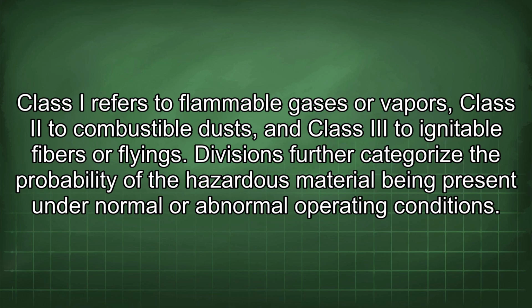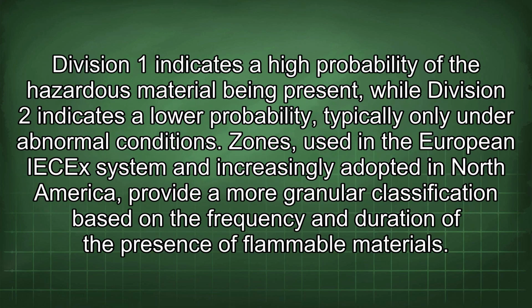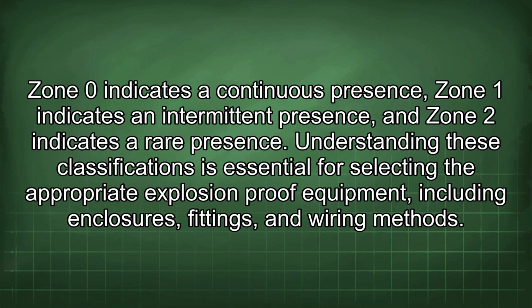Divisions further categorize the probability of the hazardous material being present under normal or abnormal operating conditions. Division 1 indicates a high probability of the hazardous material being present, while Division 2 indicates a lower probability, typically only under abnormal conditions. Zones, used in the European IEC system and increasingly adopted in North America, provide a more granular classification based on the frequency and duration of the presence of flammable materials. Zone 0 indicates a continuous presence, Zone 1 indicates an intermittent presence, and Zone 2 indicates a rare presence.